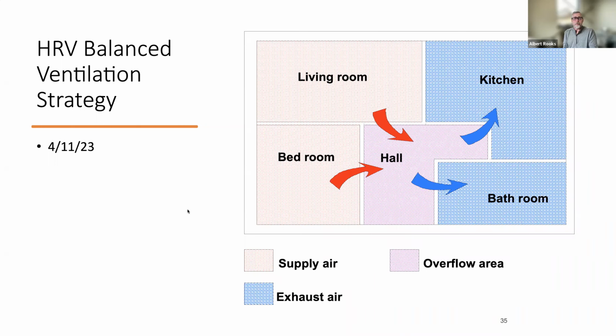If we're supplying 100 CFM in a really rudimentary way, we'll say 25 in the bedroom and 75 in the living room. It's not usually a simple number like that, but we're supplying 100 CFM to those locations, and we want another fan pulling another 100 CFM out of the kitchen and bathroom. When we do that, that's balanced ventilation. Everything flows from positive pressure areas to negative pressure areas, and it cascades and washes across the building.